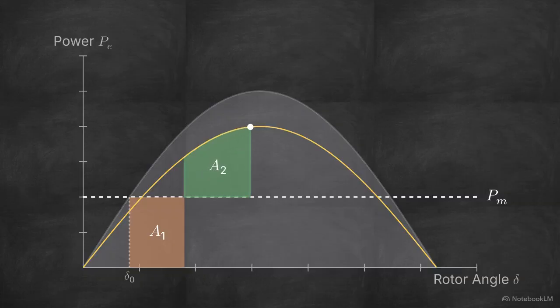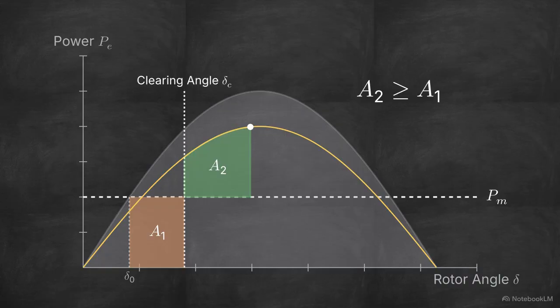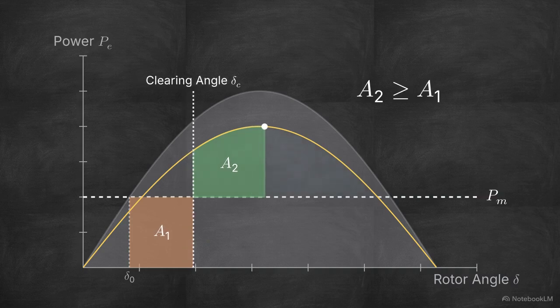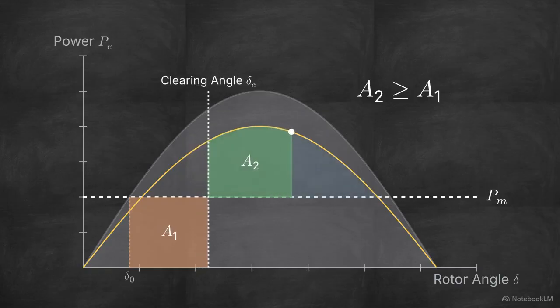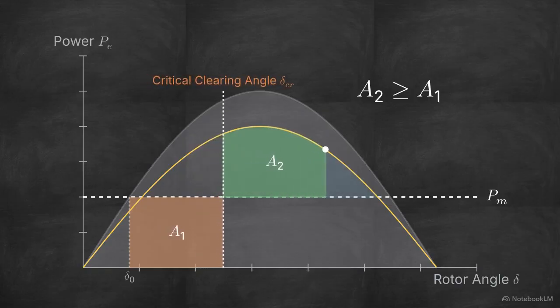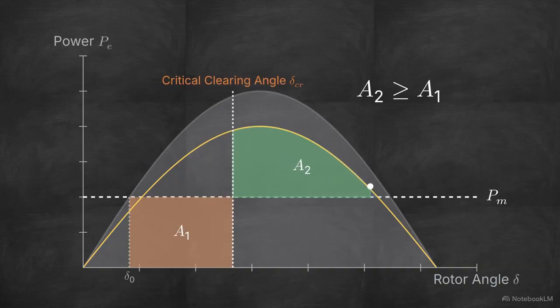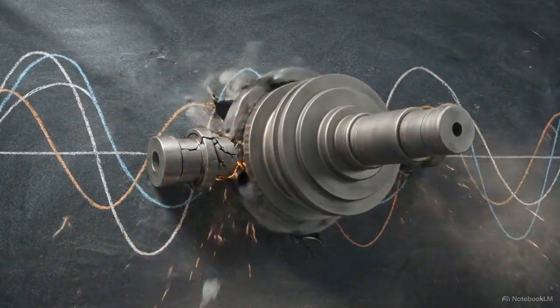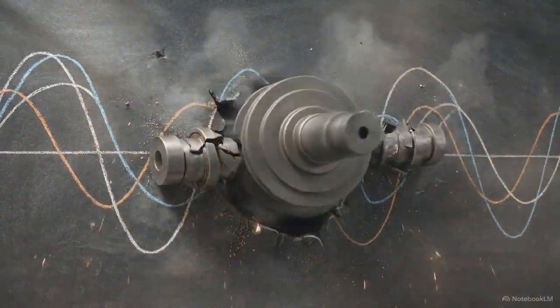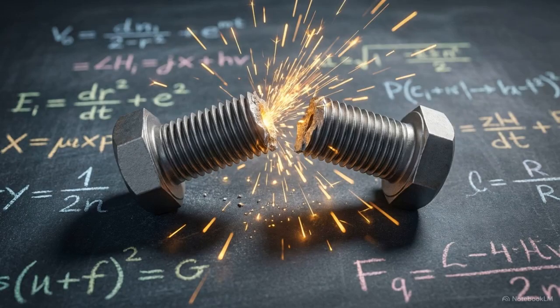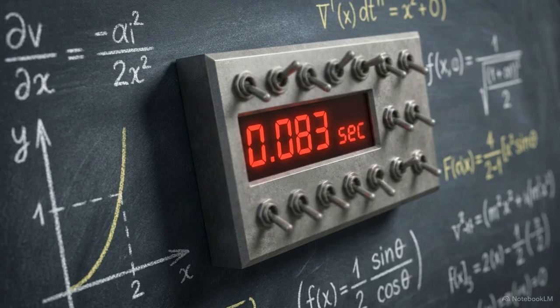The equal area criterion states the generator stabilizes only if the available deceleration area is greater than or equal to the acceleration area. The specific angle where the breakers opened is the clearing angle, delta C. If breakers take too long to open, the red area grows. The absolute limit is the critical clearing angle, where the red acceleration area perfectly consumes the maximum braking area. Opening the breakers past this critical angle is futile. The rotor will slip a pole, completely lose its magnetic lock with the grid, and be violently ejected from the system. Engineers translate this maximum angle into a critical fault clearing time.